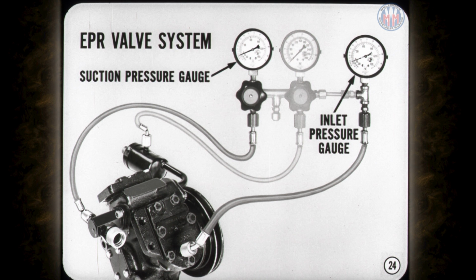For the EPR valve system, you need two low-pressure gauges, so the connections are different. Here you connect the suction pressure gauge at the left side to the suction pressure port at the rear of the compressor. The inlet pressure gauge at the right side goes to the cylinder head inlet port.